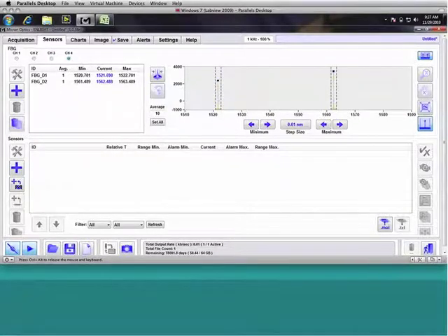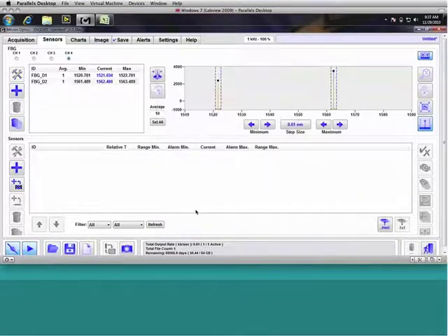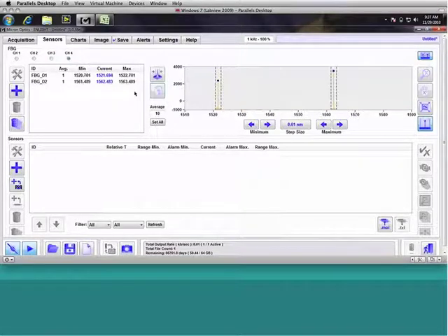And so we will do the same for our FBGs on our second fiber on channel 4, which in our example slide we had at a distance of 4,023 meters. Now I'm going to stop short of assigning the distance on the second one to point something out. Distance compensation is enabled on a per channel basis. So if we go back to channel 3, we notice that this icon is depressed and it's got a blue background. If we go to channel 4, it's not. So these are independent controls on a per channel basis.